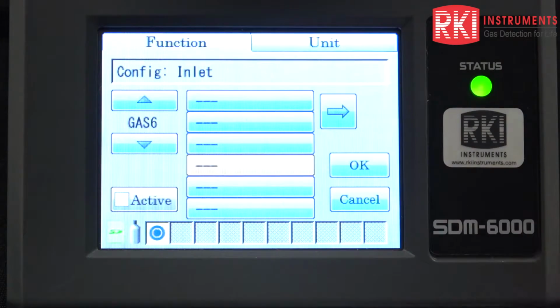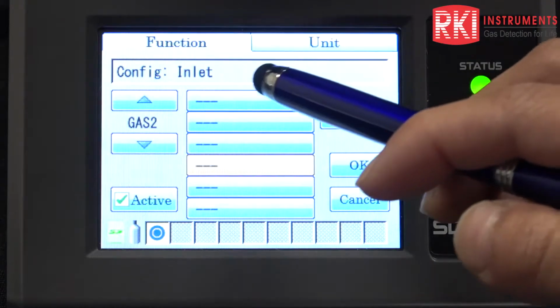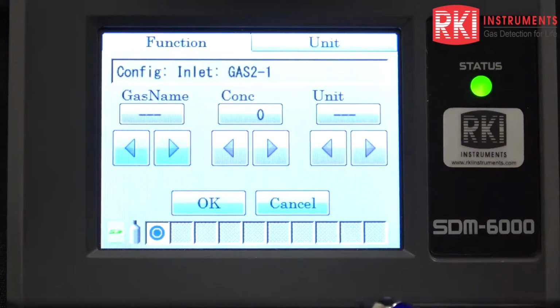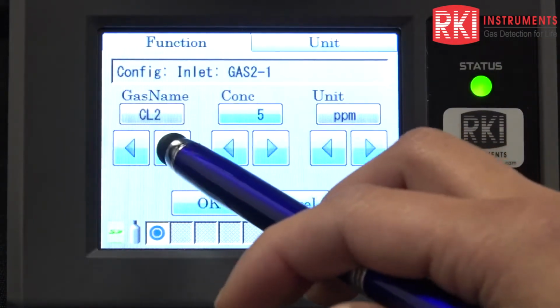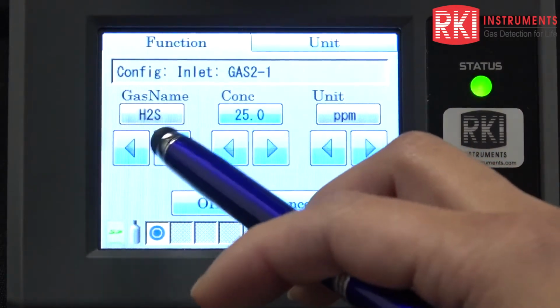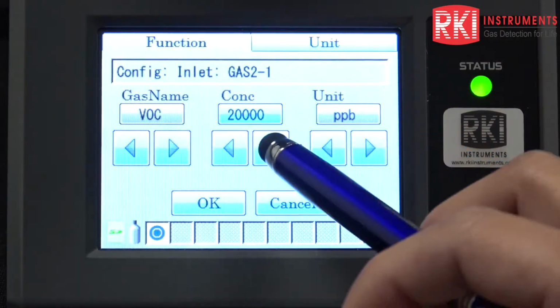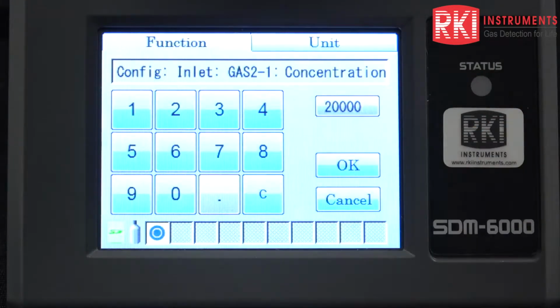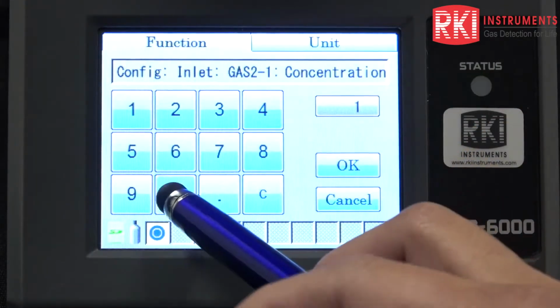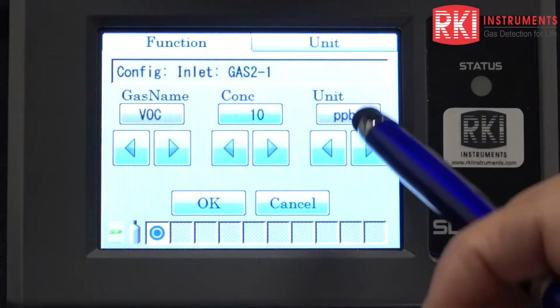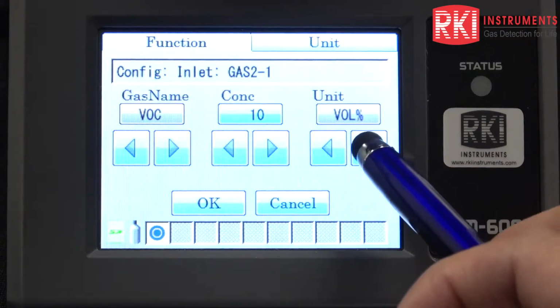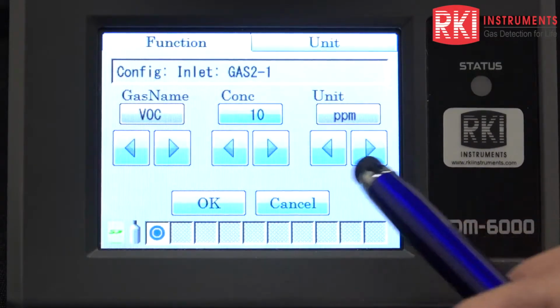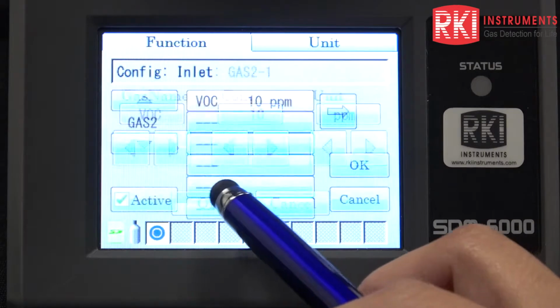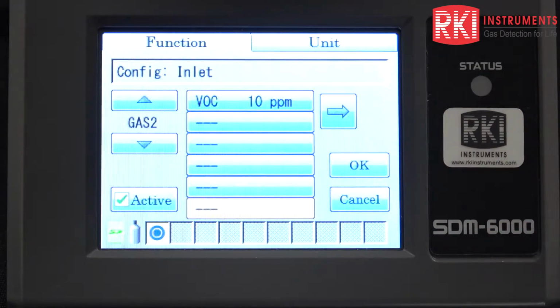I'm going to go to gas 2. This one, I have isobutylene 10 parts per million. So I'm going to go in, press the arrow, make sure it says VOC, and it's 20,000. That's not what I have. I have 10. So I can actually input 10. And it's ppm, not ppb, so I need to change that. And okay. And that's pretty much how you set up your inlet.